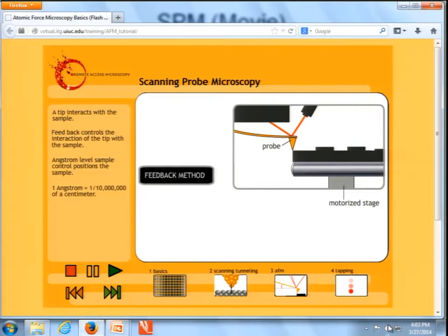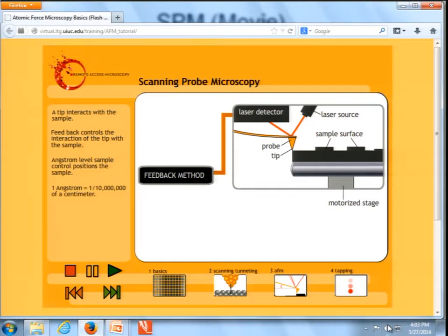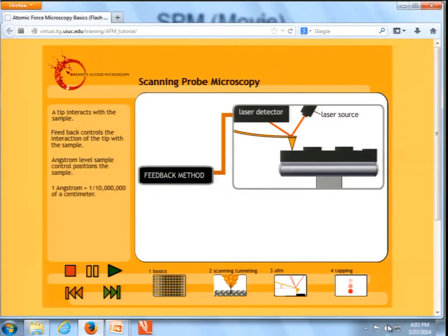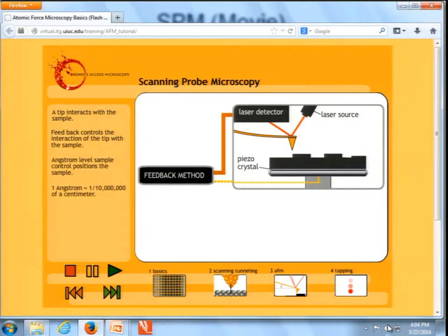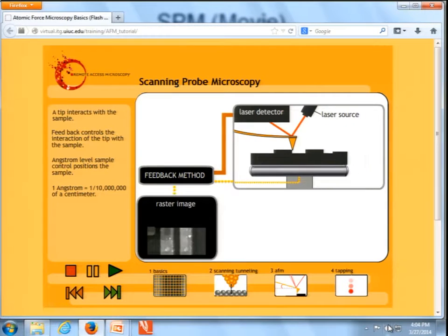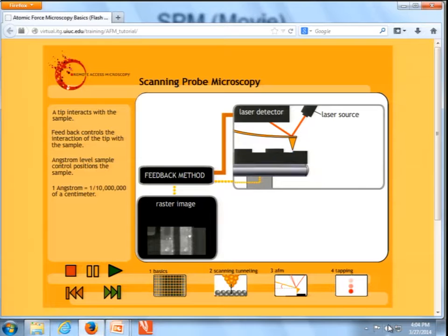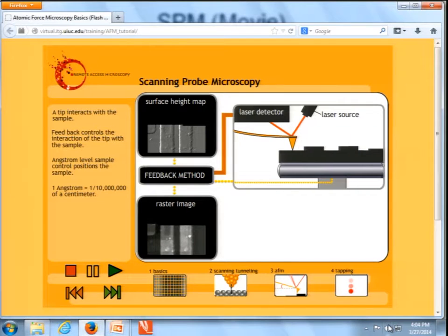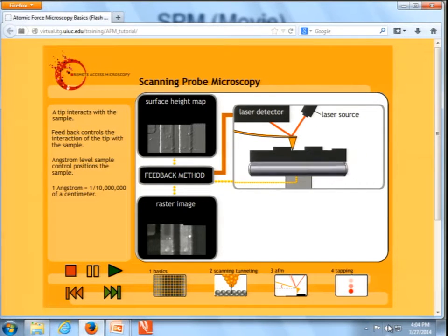All scanning probe techniques have a small probe, a feedback method, and fine control of the distance between the tip and the sample surface. The feedback control assesses that distance. If the distance is too small, the feedback loop signals the piezo crystal to contract, lowering the sample. If the distance is too large, it signals the piezo crystal to expand, raising the sample. An image is created by plotting horizontal and vertical movements as the tip scans across the surface. An image of the feedback signal is also produced, indicating how well the feedback loop is controlling the tip-sample interaction.